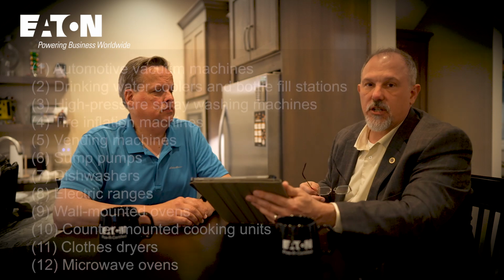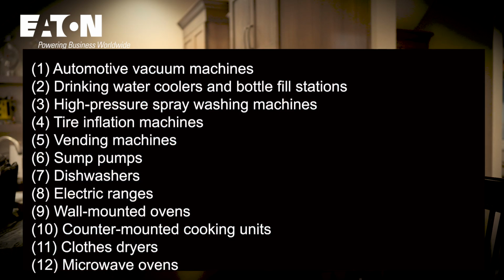D is GFCI protection for branch circuits or outlets that supply appliances, and they have a list of 12 appliances rated 150 volts or less to ground and 60 amps or less, single or three-phase. I'll just throw the appliance list on the screen so you see them. I'm not going to read through each of those, but those are a list of appliances that we've recognized have had a body count associated.